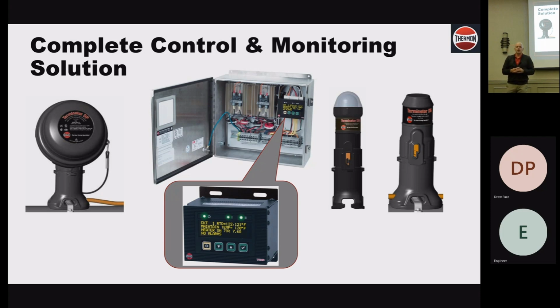That's a really common thing with alarms. The plant goes down or you put part of it out for an outage, everything gets cold, the heat trace is firing, and you're getting alarms all over the place, and people go, yeah, it's an outage. What they don't realize is one of those is a GFI trip. Then they bring the plant back online, but nobody went to the panel and clicked the GFI trip, so now your heat trace is off. That's one of the major problems when people don't have a smart control system and just start ignoring the lights.